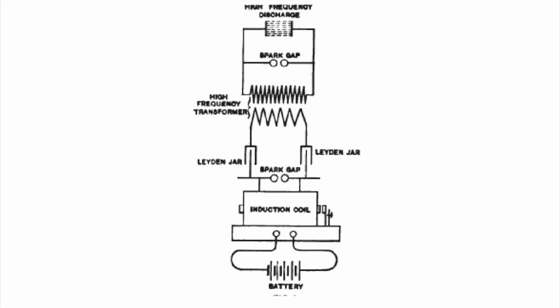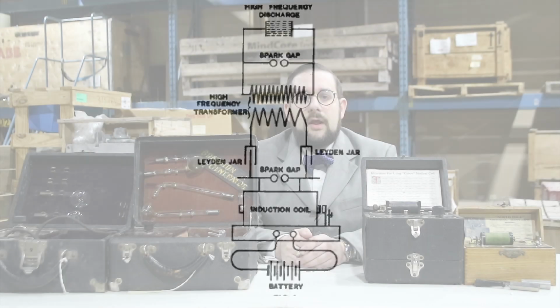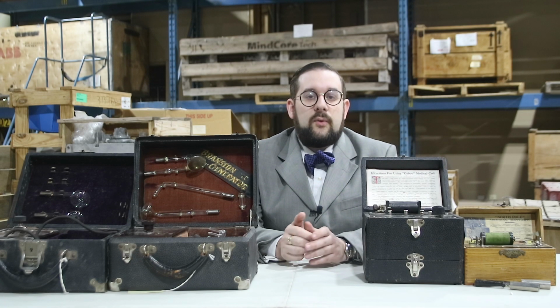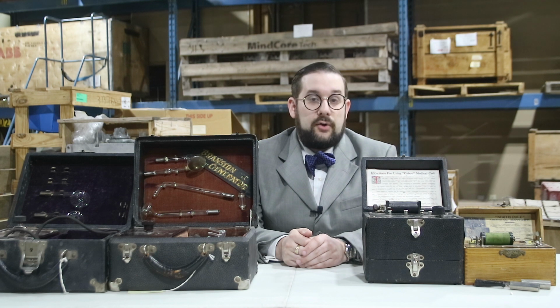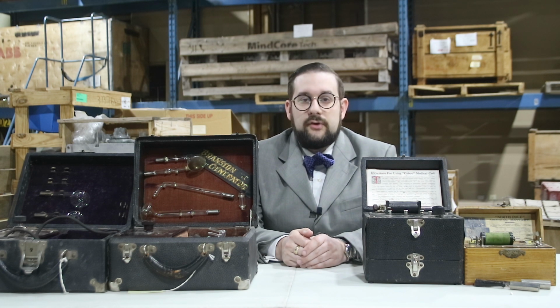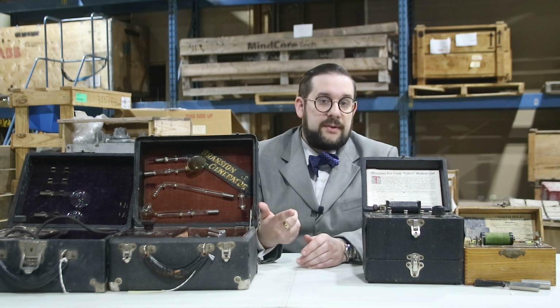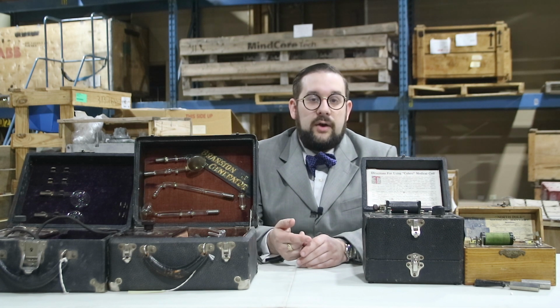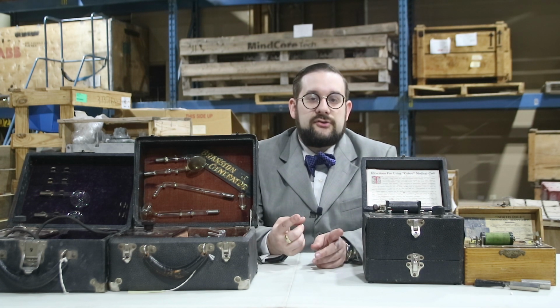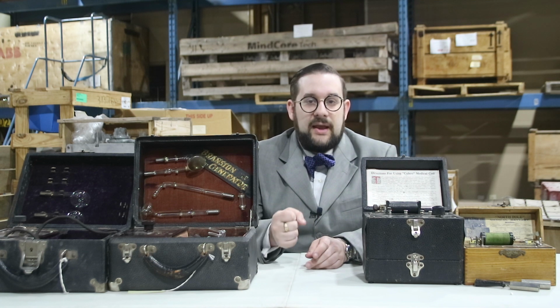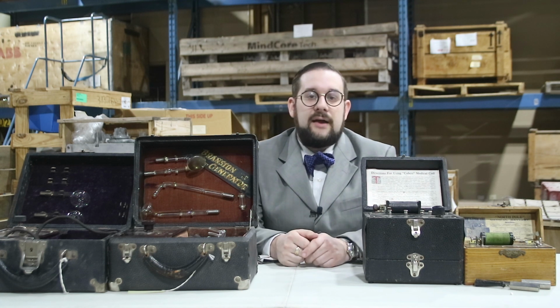And here, the secondary coil is not directly connected to the primary coil, but rather magnetically coupled to it. It's separate. So the high-frequency magnetic field produced by the primary coil is picked up by the secondary coil and stepped up to a higher voltage. So what's interesting to note here is that when it was first designed, the Oudin coil was monopolar, meaning that one end of its coil was grounded, leaving just one electrode for applying to the patient. Whereas the Tesla coil was bipolar. It had two electrodes coming off the coil, one end of which the patient would grip, while the other would be wielded by the doctor.